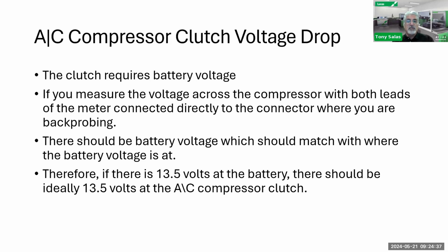So if I have 2 volts dropping across my positive lead of the compressor to positive battery, that tells you there's a problem on the positive side. When voltage drop tests are lower than what's required from battery voltage, that means you've got a high resistance fault somewhere. That's what we're trying to identify.